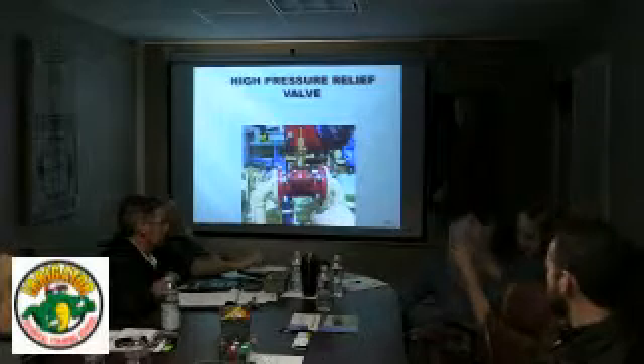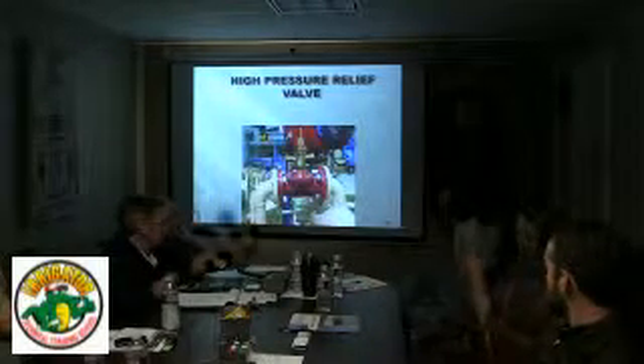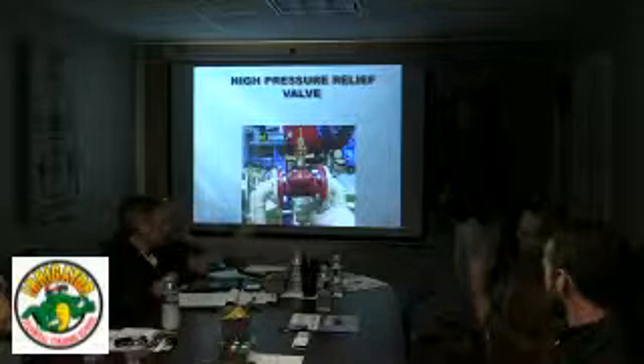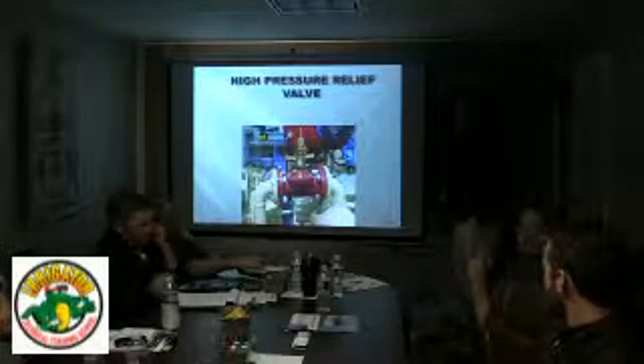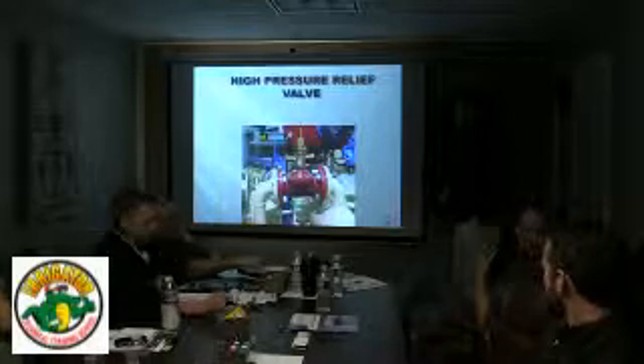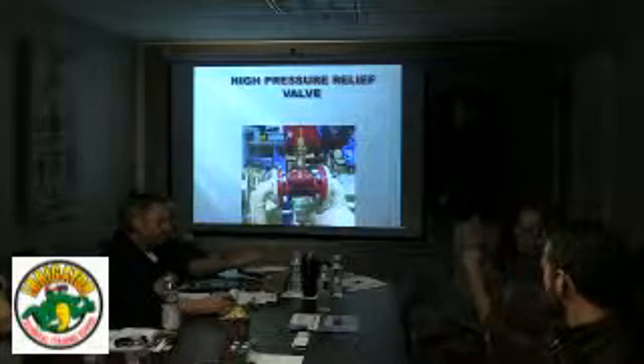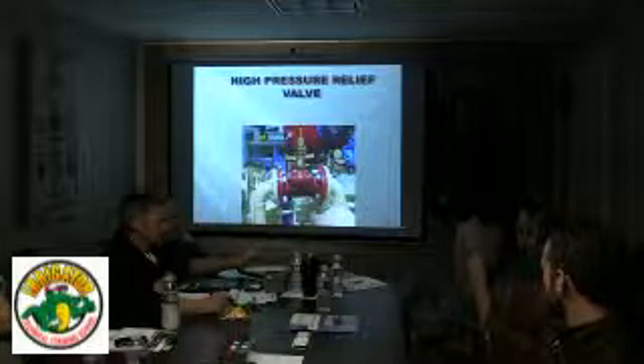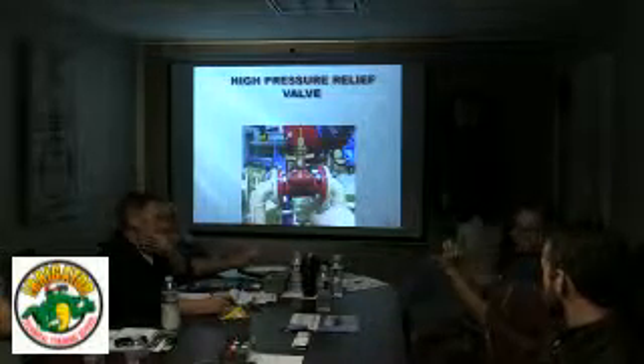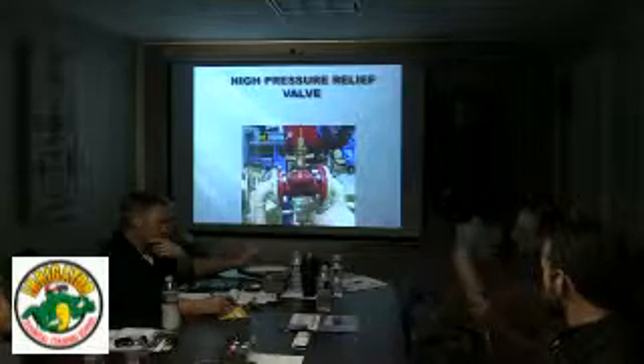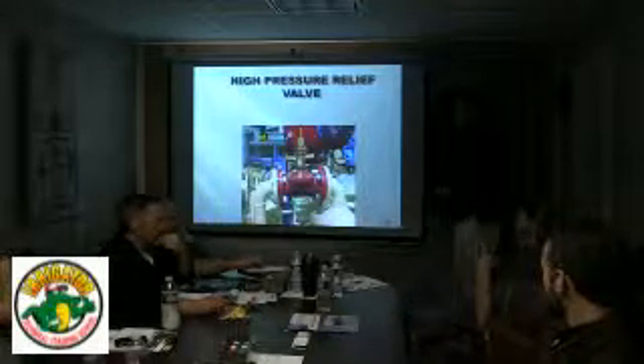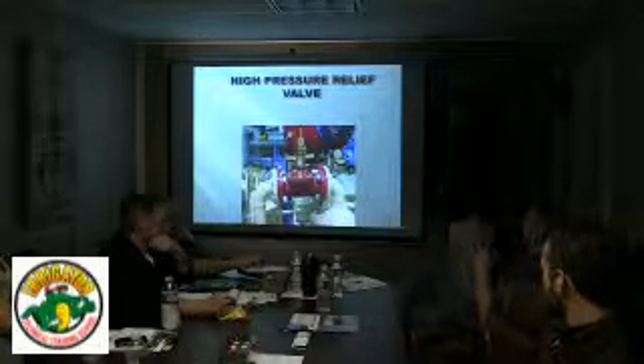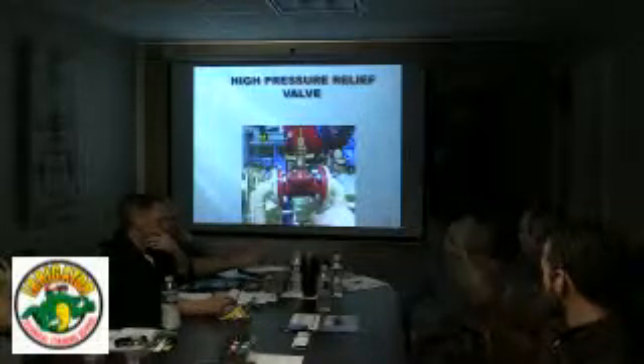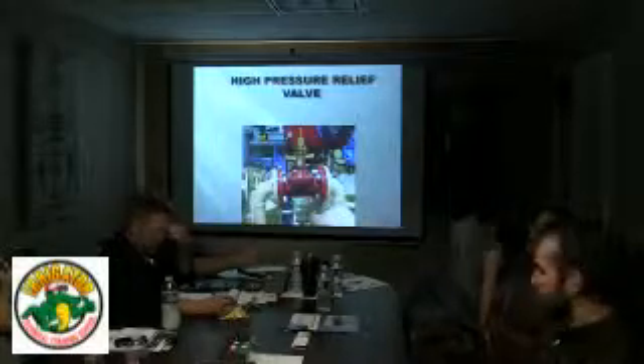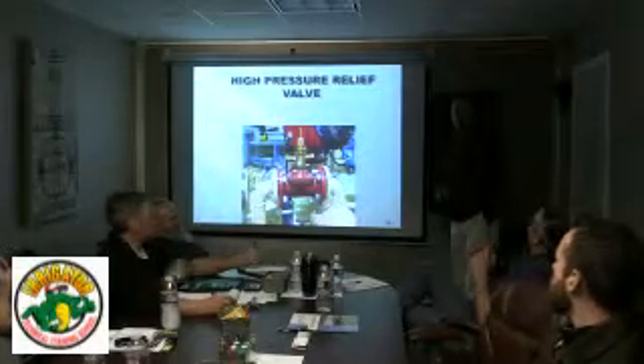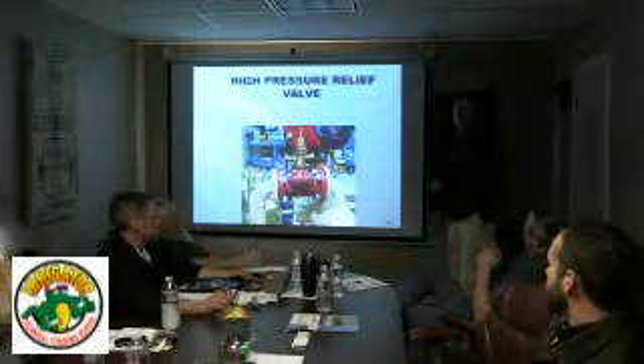More realistic. But still, even if your valve is not running, you want to check your ports. I don't know about your water quality, but out here you get buildup around the pressure ports, especially the smaller ones, the 1/4 inch ones. The bigger ones, the 1/2 inch or 3/4, get buildup too, and that will cause a problem with the valve not functioning, not even opening. Guys say my valve never opens. Well, guess why? It's shut. It'll never open. It can depend if it's real silty water, and I've seen other places where it's real scaly and builds up.